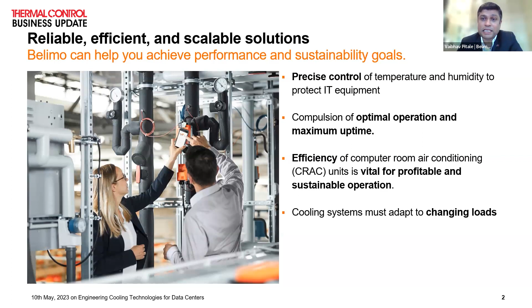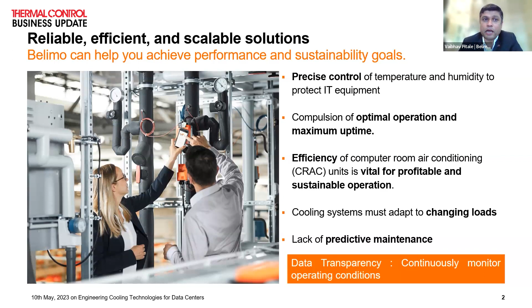In India, we are used to preventive maintenance, but it's important to move toward predicting problems before they happen, since uptime is critical in a data center. If I know where the problem is, I can take action. If I don't know the water flow through the system, the temperature in a particular room, or the relative humidity, how am I going to take action? So data transparency and continuously monitoring operating conditions become very important.